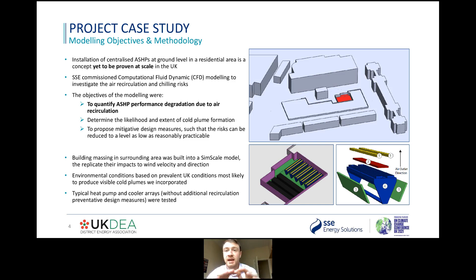And what we essentially did was test a typical heat pump and cooler array without any preventative measures, so a base case, just to see what the effect of it was. And once we did the initial modelling, the effect of it was this quite scary picture, which we see in this slide. So there are lots of pictures here, so I'll take time going through these, but we based the initial modelling on V-bank and flatbed coolers, different orientations of plant. Obviously, we did the base case to mitigate visual impact and equipment footprint. So what became very apparent very quickly is that the negative effects of the air recirculation that we discussed in this base case were very severe.